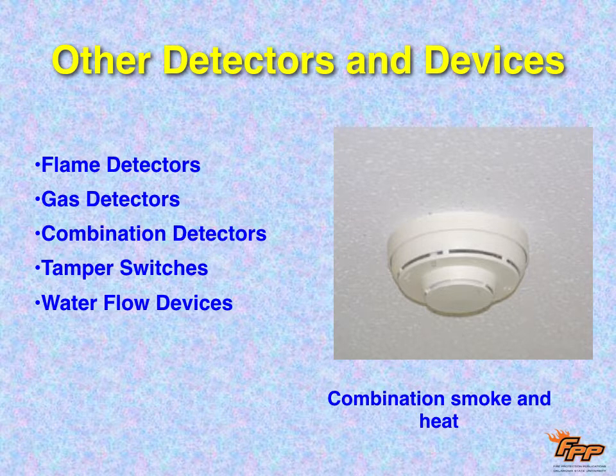There are other types. There's flame detectors, gas detectors. You all have one in your home, carbon monoxide. There's combo detectors. Now, there's a couple other types, tamper switches. Tamper switches tell the fire alarm company if somebody is turning off the system. So if you were an arsonist, you'd want to shut down the fire sprinkler system if you wanted to burn a building down. So if you start shutting down the fire sprinkler system, it's going to sense that. As soon as you turn it a couple of turns, it sends a message to the alarm company telling them that somebody's turning it off. And they'll send a message either to the owner or to the fire department.